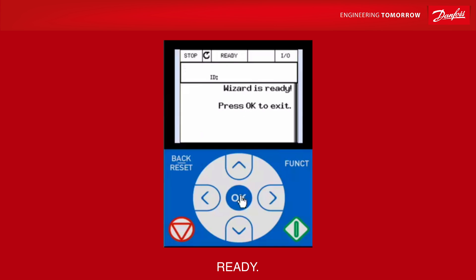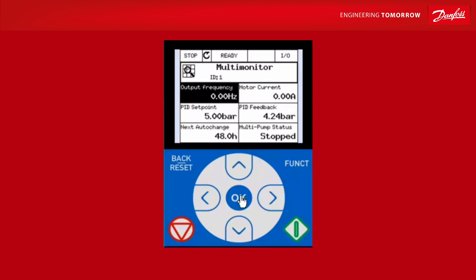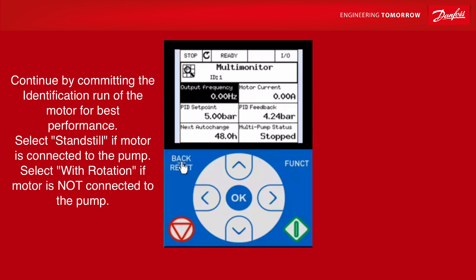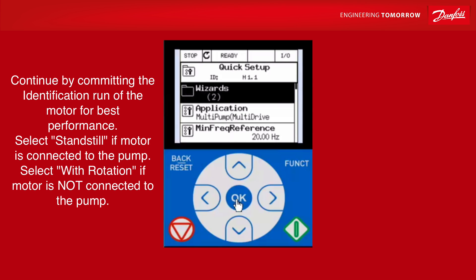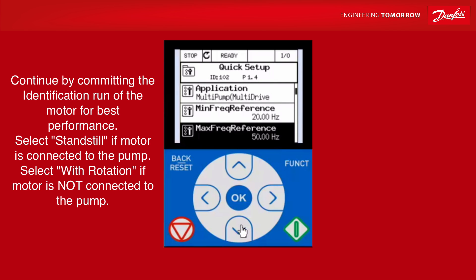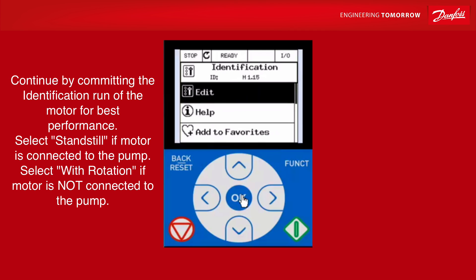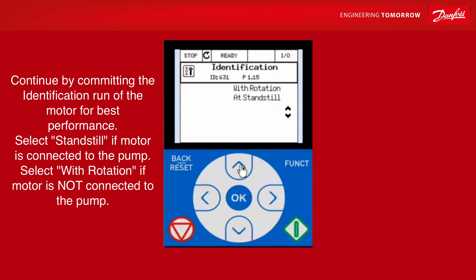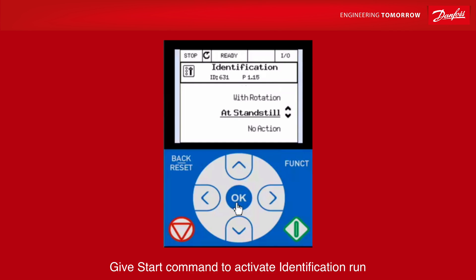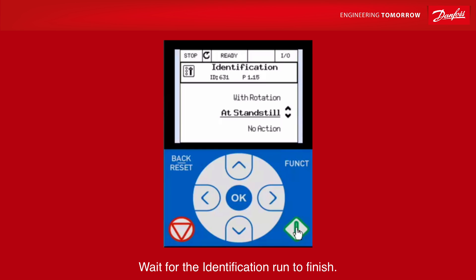Then we are ready. Continue by completing the identification run of the motor for best performance. Select standstill if motor is connected to the pump. Select with rotation if motor is not connected to the pump. Give start command to activate identification run. Wait for the identification run to finish.